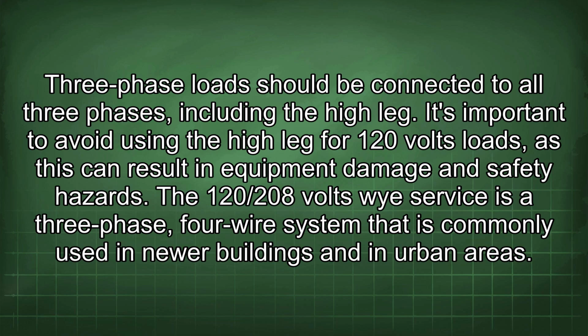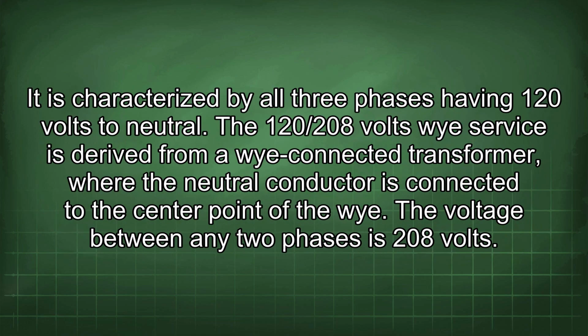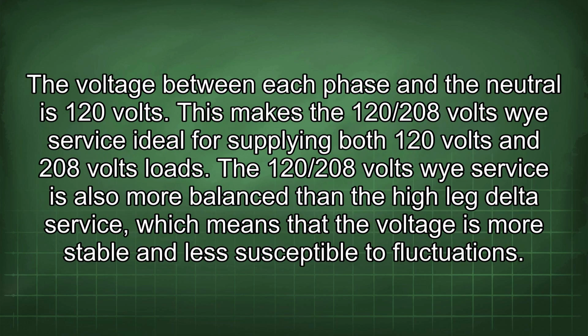The 120/208 volts Y service is a three-phase, four-wire system that is commonly used in new buildings and in urban areas. It is characterized by all three phases having 120 volts to neutral. The 120/208 volts Y service is derived from a Y-connected transformer, where the neutral conductor is connected to the center point of the Y. The voltage between any two phases is 208 volts. The voltage between each phase and the neutral is 120 volts. This makes the 120/208 volts Y service ideal for supplying both 120 volts and 208 volts loads.